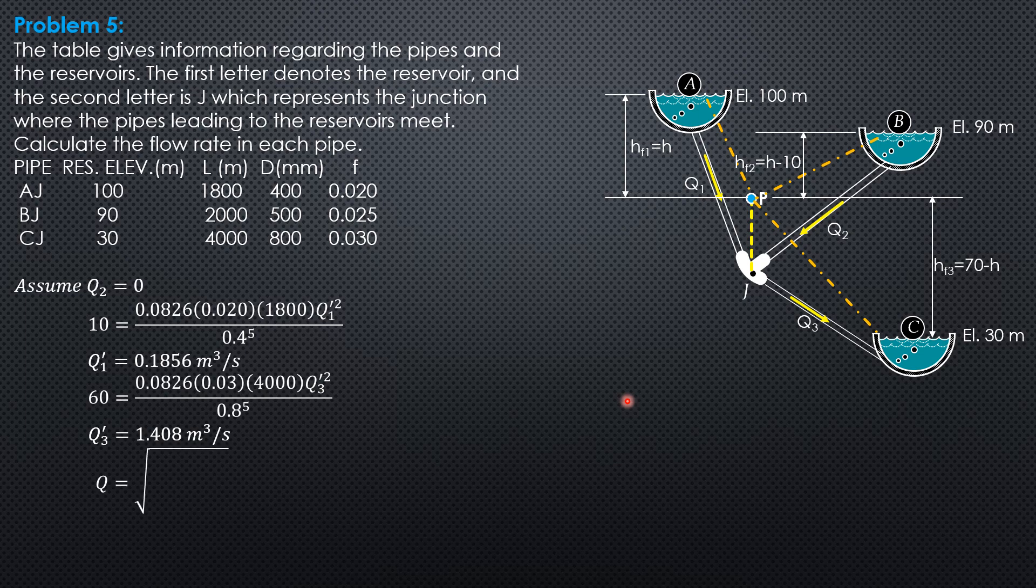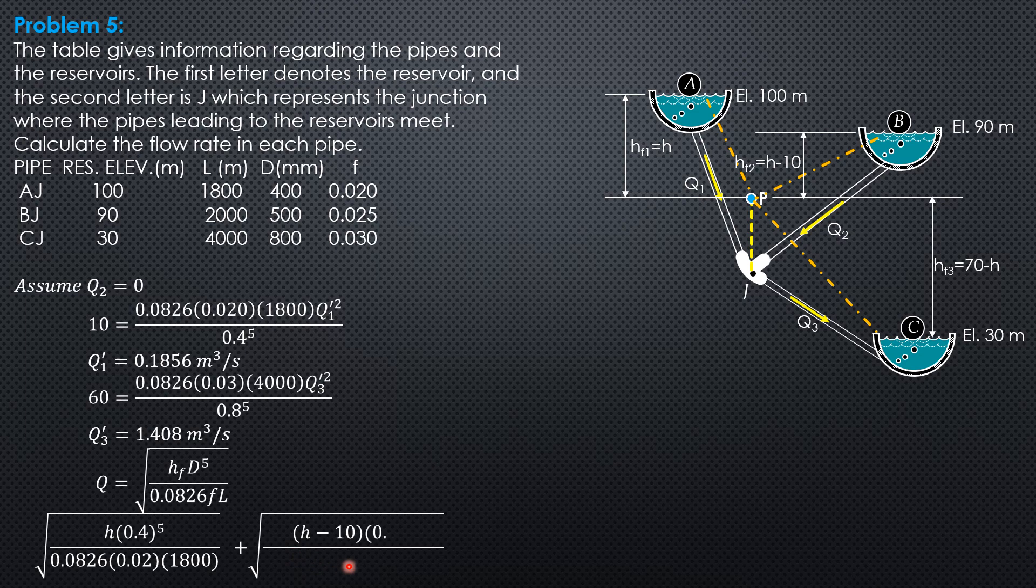So discharge formula: Q equals square root of HF diameter to the fifth over 0.0826 friction factor length. And the equation is Q1 plus Q2 equals Q3. So Q1 is square root of H times 0.4 to the fifth over 0.0826 friction factor 0.02 length 1,800, plus Q2 square root of quantity H minus 10 times diameter 0.5 to the fifth over 0.0826, 0.025, length is 2,000.